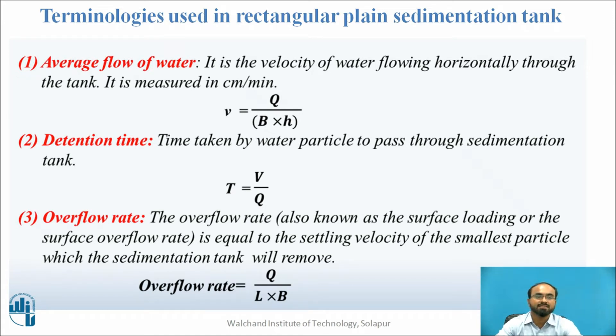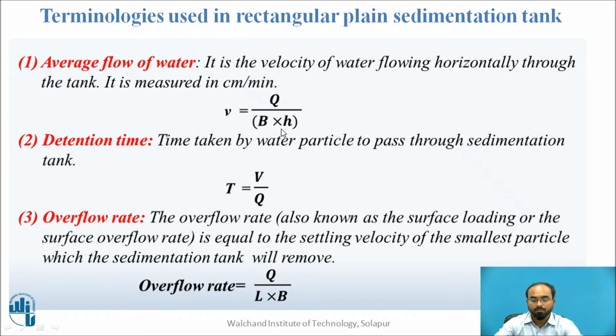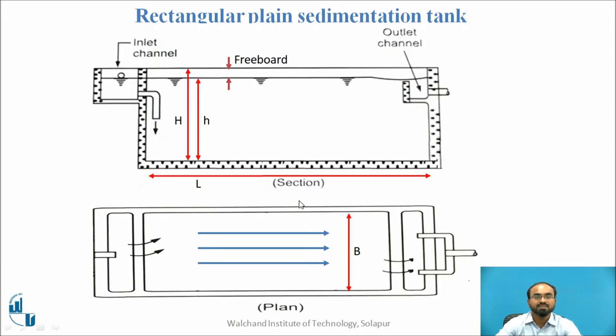The major focus is on three parameters. First is average flow of water — it is the velocity of water passing horizontally through the tank, measured in centimeters per minute. The formula is: small v equals capital Q (discharge) divided by breadth B into small h (effective height of water). This represents the cross-sectional area of the rectangular tank.